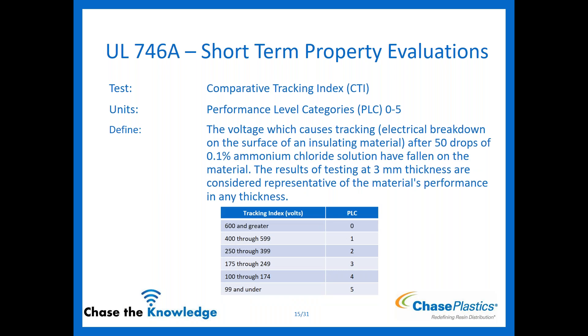CTI — Comparative Tracking Index — is the voltage which causes tracking, also known as electrical breakdown on the surface. PLC values apply here as well: 600 volts or greater gives you a zero, all the way down to under 100 volts gives you a five. Lower number means better performance.